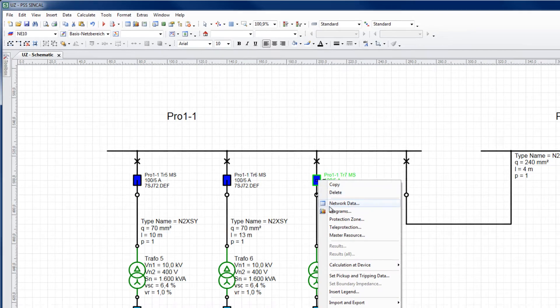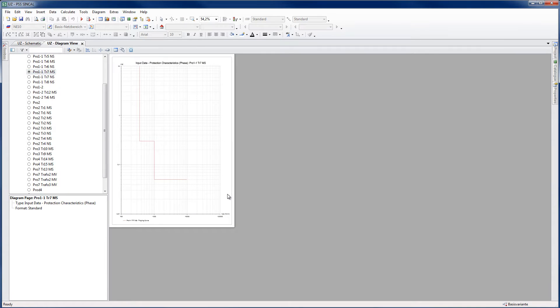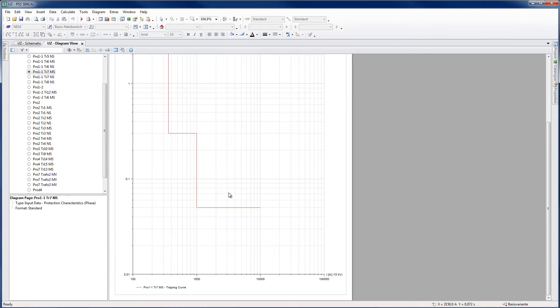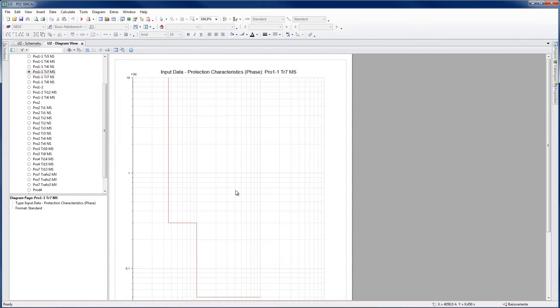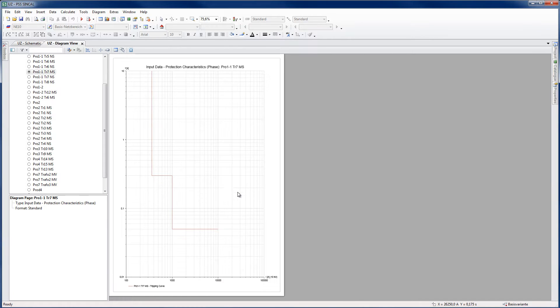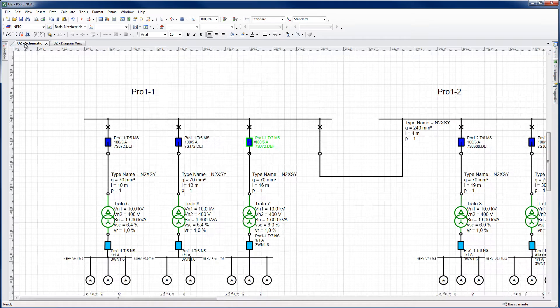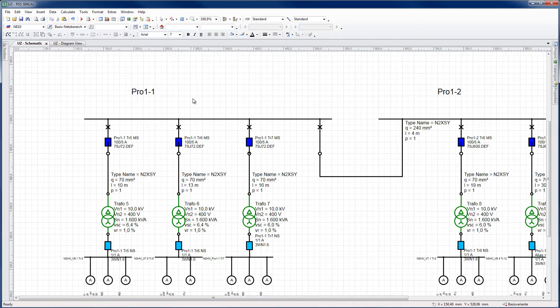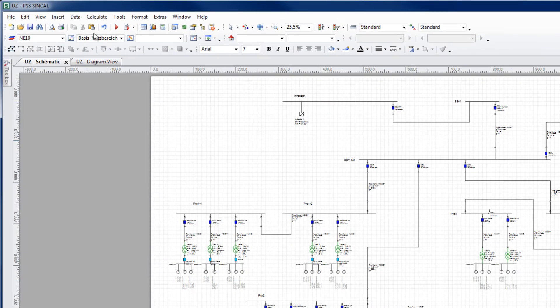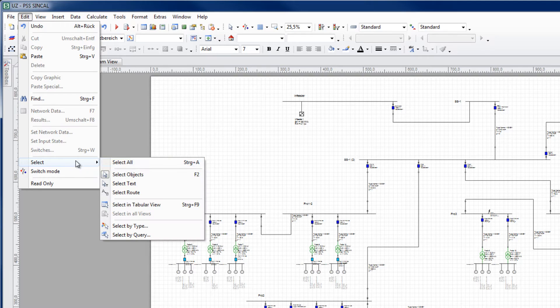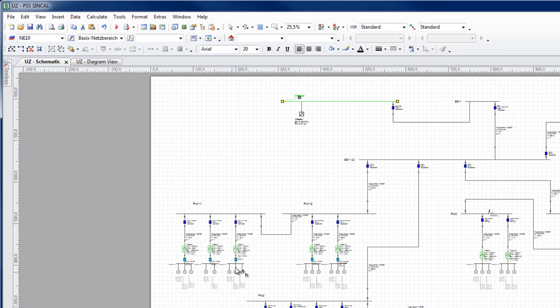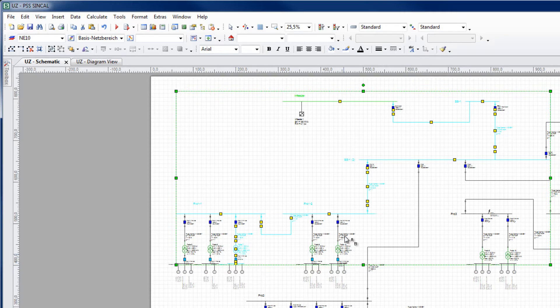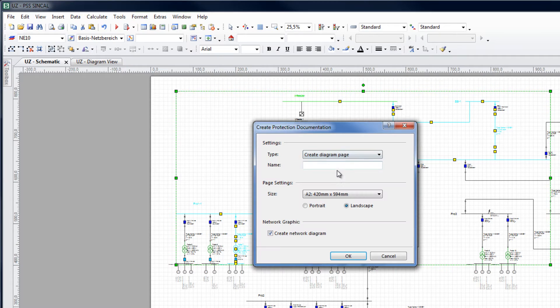The settings of the device can be easily visualized in a double logarithmic current time diagram. Particularly useful for the protection coordination of overcurrent devices in radial networks are grading diagrams. These are in-built in the protection documentation. First, a protection path needs to be selected. This can be done through the use of the route selection tool. Once a path is selected, create the protection documentation through the Tools menu.